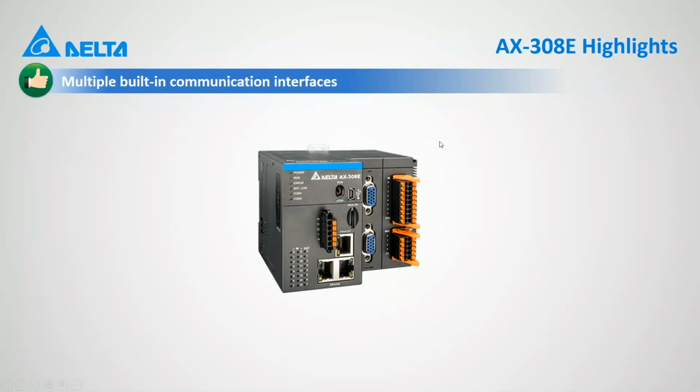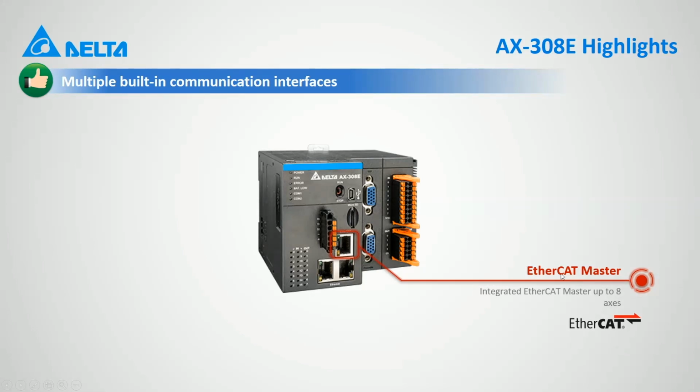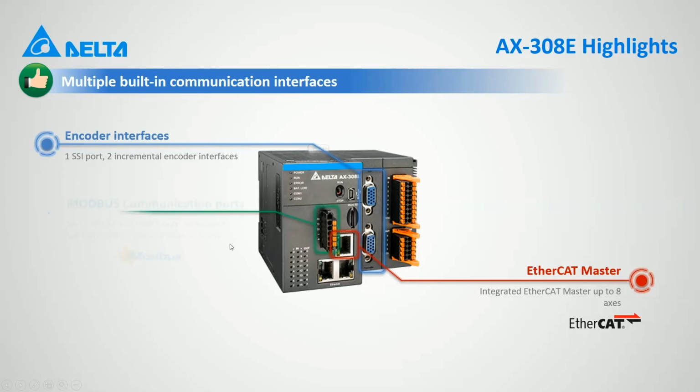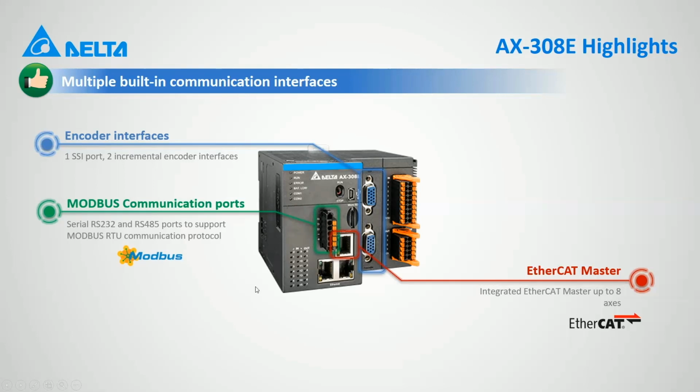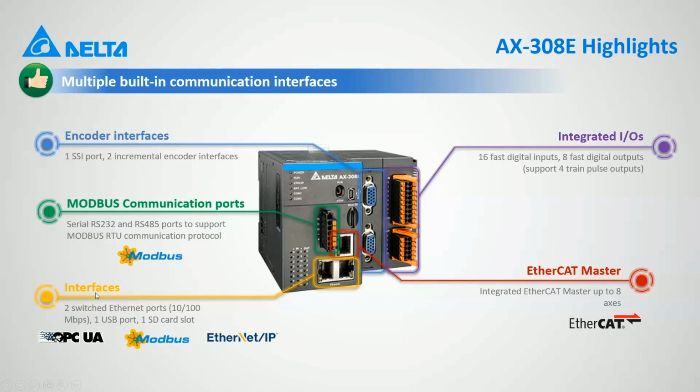Okay, the AX308E supports many different communication protocols and has many different embedded interfaces. Of course, there is an EtherCAT port, this one, which is able to support up to 8 axes. Like the AS500 and the DVP series, there is one SSI port to support the absolute encoders and two incremental encoder interfaces. There are also two serial ports, RS232 and RS485. An integrated port with 16 digital inputs and 8 digital outputs. In addition, there are two switched Ethernet ports. Switched means with one IP address, even though the ports are two, which support Modbus TCP, EtherNet/IP, and even OPC UA, which is the latest trend in communication technology.